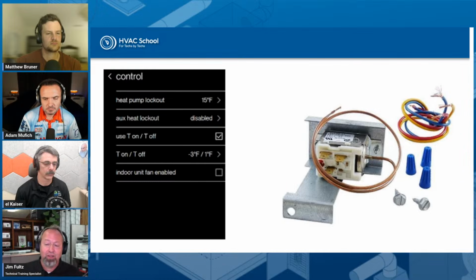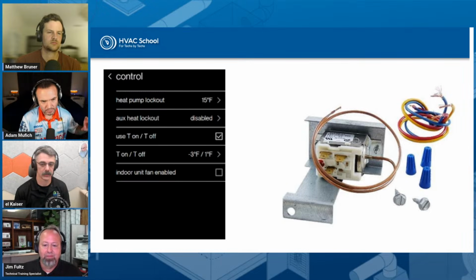But at this point, with the low temp compressors and everything that we got going on, there's less and less value for even cycling that heat pump off outside. Nice. I would never cycle a heat pump off. If my auxiliary resistance, or my secondary heat source, let that sucker run. A lot of different thermostats, like Sensi, and the communicating systems like Carrier, Trane, Daikin, Mitsubishi, actually look at an outdoor thermistor in the outdoor unit, which is sensing the outdoor temperature. So you don't have to run an extra wire to monitor the outdoor.